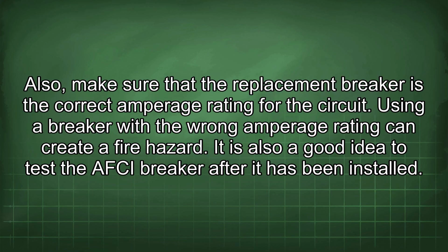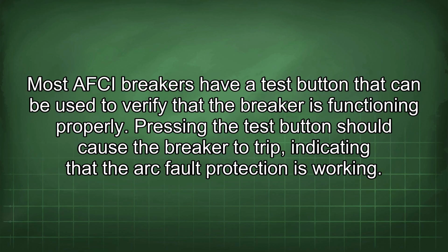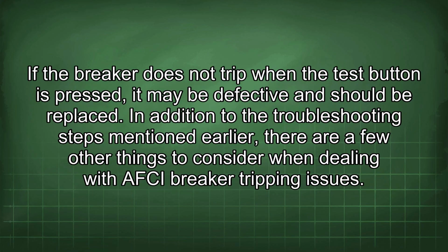It is also a good idea to test the AFCI breaker after it has been installed. Most AFCI breakers have a test button that can be used to verify that the breaker is functioning properly. Pressing the test button should cause the breaker to trip, indicating that the arc fault protection is working. If the breaker does not trip when the test button is pressed, it may be defective and should be replaced.